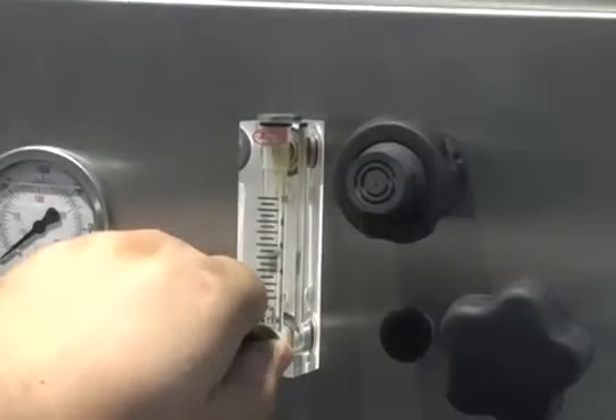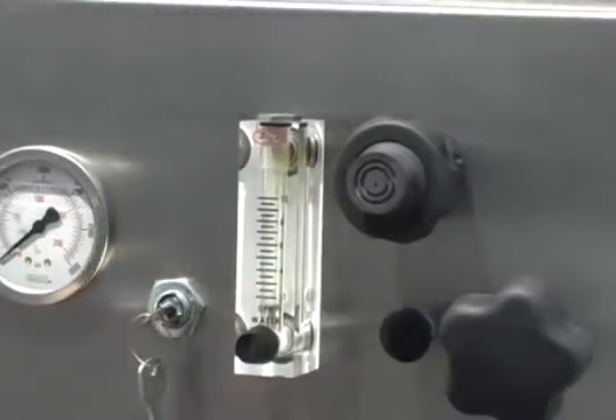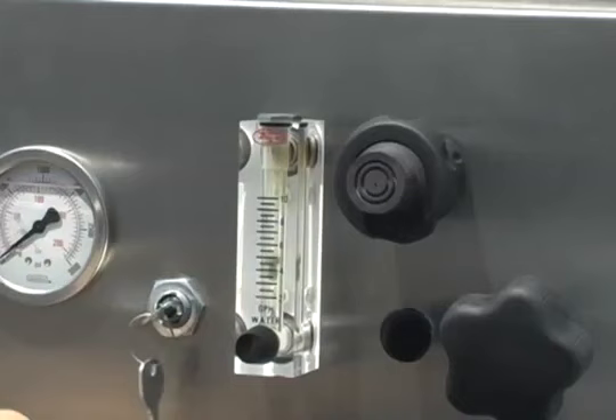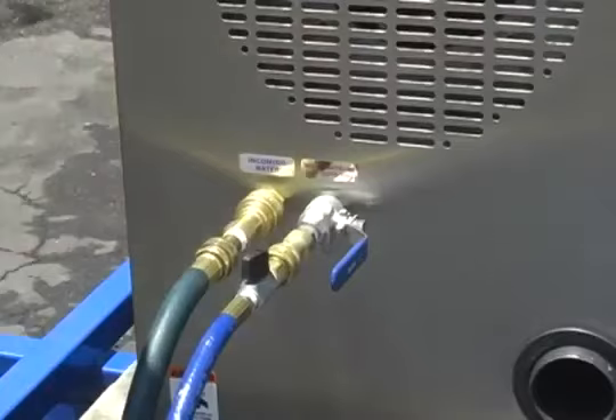5:1 means that you would set your meter where the bubble would rise to 5 on the level. This happens only in the first few seconds, so be quick about setting this. Once the water level is full in the reservoir tank, you will not be allowed to adjust the meter unless you reconnect the bleeder hose and bleed out some of the extra water so that you can reset your mixture valve. Now your machine is ready to go.